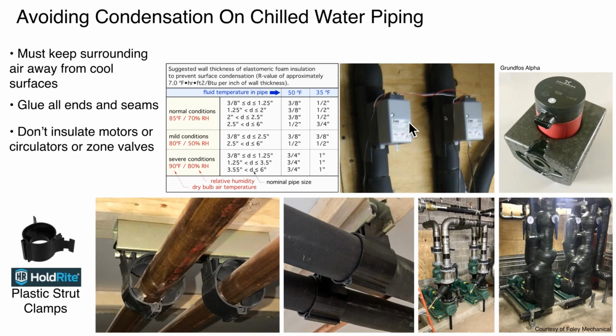One final photo up here, zone valves. Don't insulate the motors. That also applies with circulators. The volute should be insulated, but make sure you leave the actuator or the motor of a circulator uninsulated because it has to dissipate heat, especially if it's also being used in a heating mode operation.